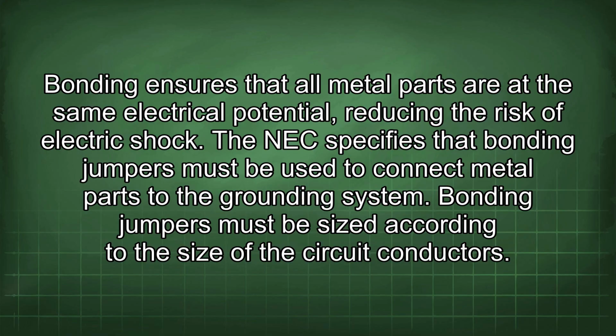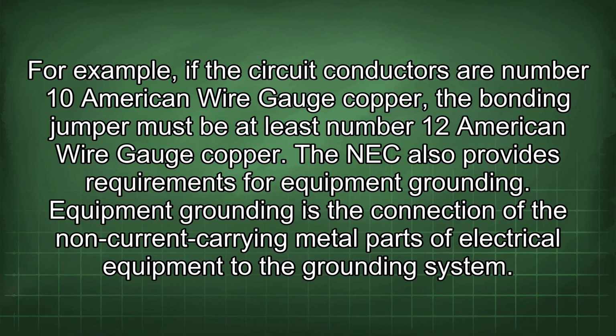The NEC specifies that bonding jumpers must be used to connect metal parts to the grounding system. Bonding jumpers must be sized according to the size of the circuit conductors. For example, if the circuit conductors are number 10 American wire gauge copper, the bonding jumper must be at least number 12 American wire gauge copper.